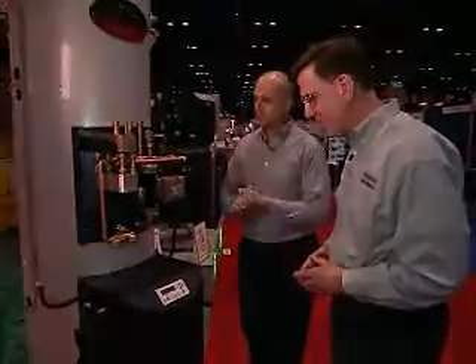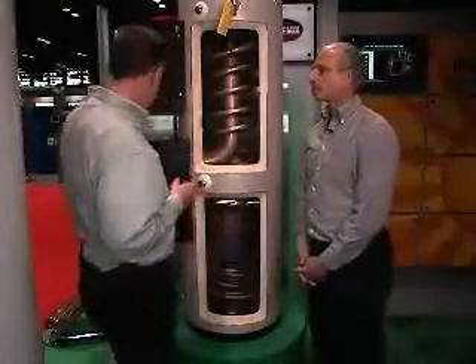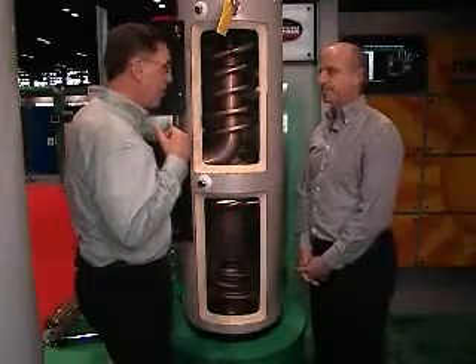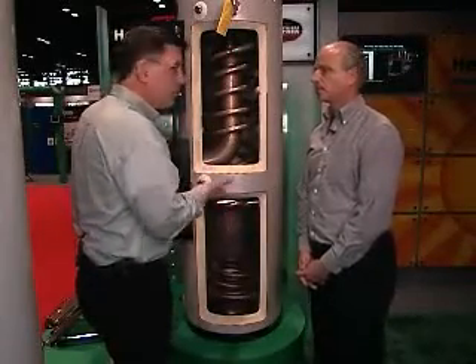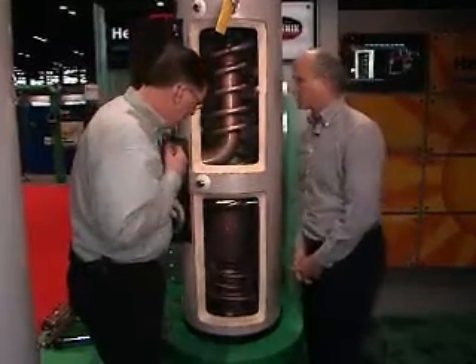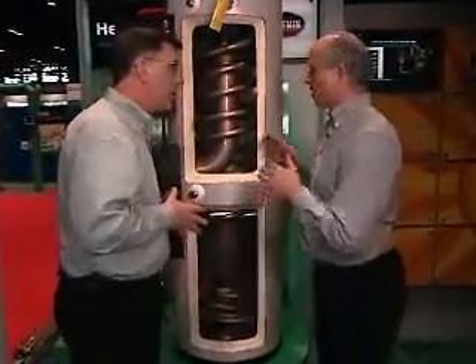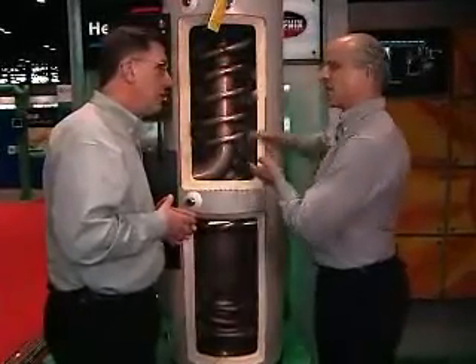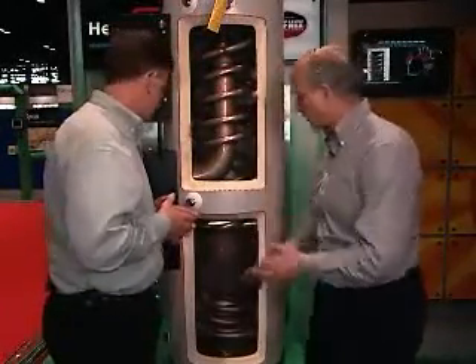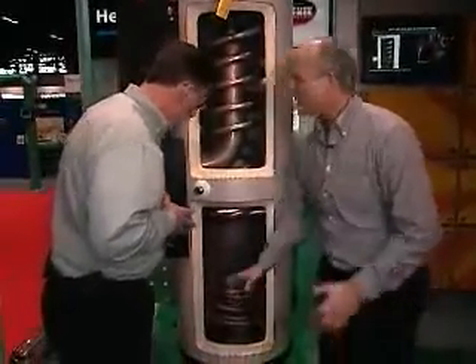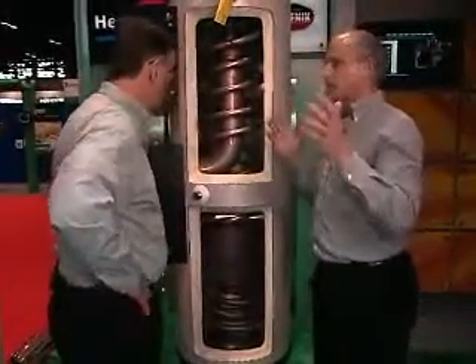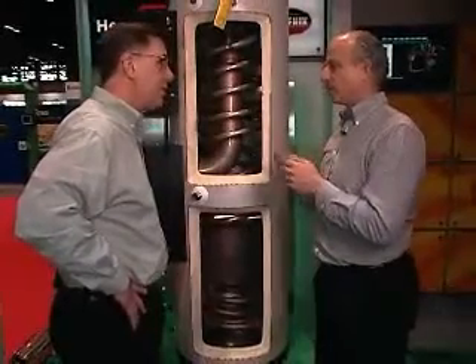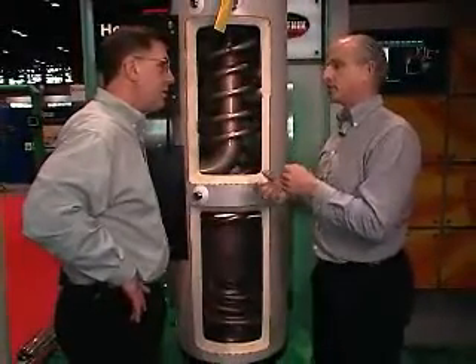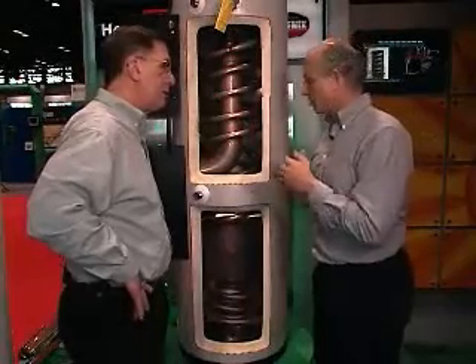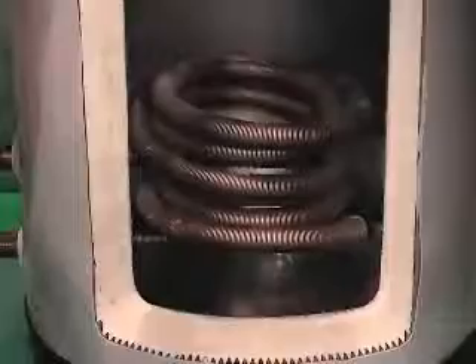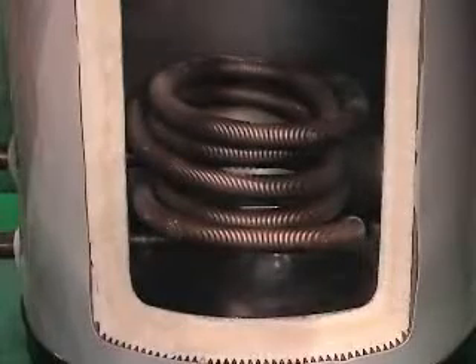Very nice. So we got the Phoenix Plus Solar, and this package is what we just looked at? Yes, it is. The hydronics package? Yes, it is, mixing solar with our combustion system. Essentially, Dan, all we did was take our combustion system and raise it up in the tank, and then we added this solar heat exchanger. If you have panels on your roof and you have solar, we've designed the system so that we integrate the solar into our entire package.